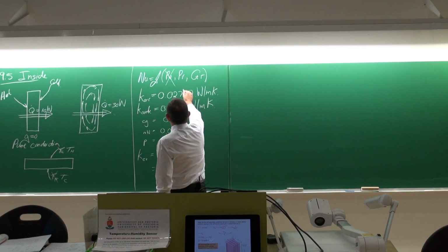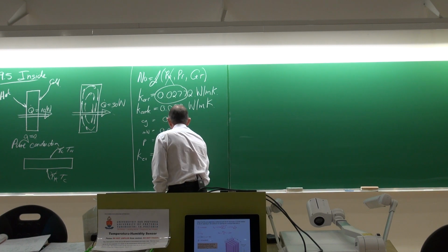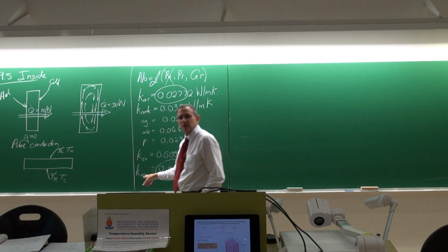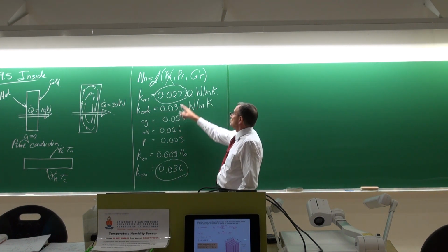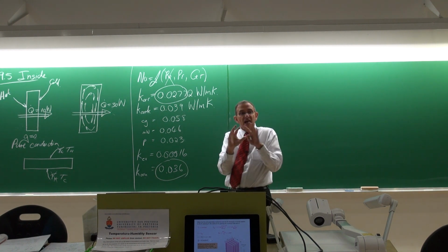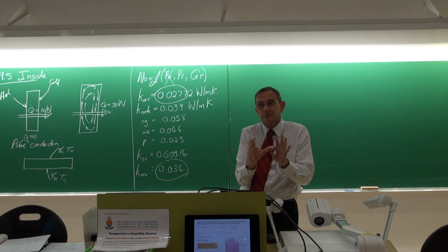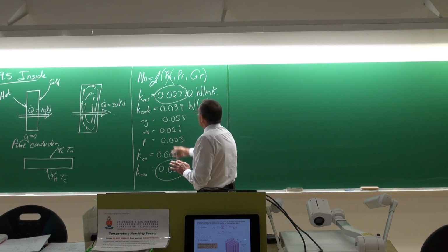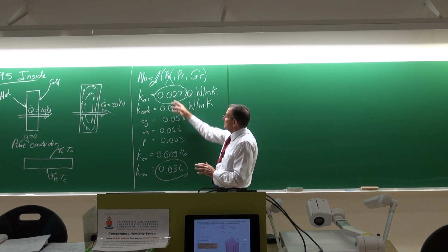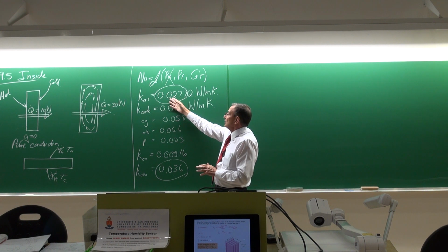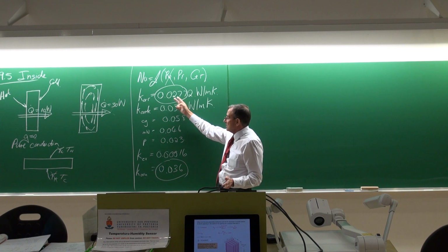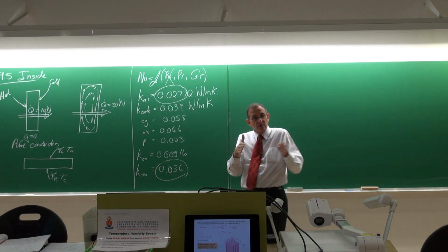Okay. So again, if we now compare that to that, then I think the question that you can ask is, but why do you use Armaflex? Why don't you use air? Okay. These values of air would be when the air is stationary. It is not moving. So that will work in an environment where G is equal to 0. But because of the natural convection, this value for the K will be much higher, maybe 3 times higher or something like that.